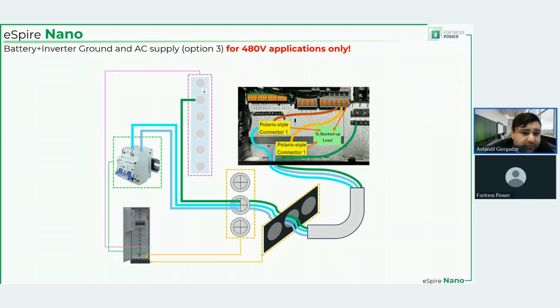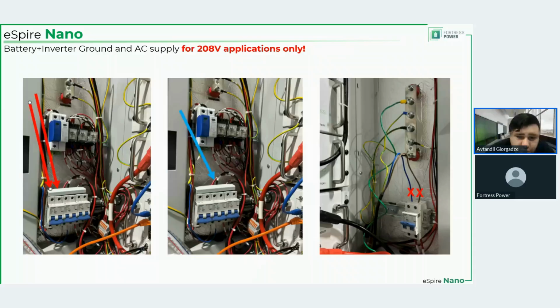For 208 volt, what you do instead is you don't connect anything on that breaker on the right side, nothing whatsoever. The cables that are connected to it from the factory, they're totally fine, but nothing on the other side. And you connect those 208 volt line cables, phase 1, phase 2, phase 3, doesn't matter, 2 line cables from 208 volt Y configuration to this breaker, because this breaker has continuity with the other 2 breakers, like continuity L1 to L1, L2, L2, that type of thing. You deliver 208 volts here, yes.